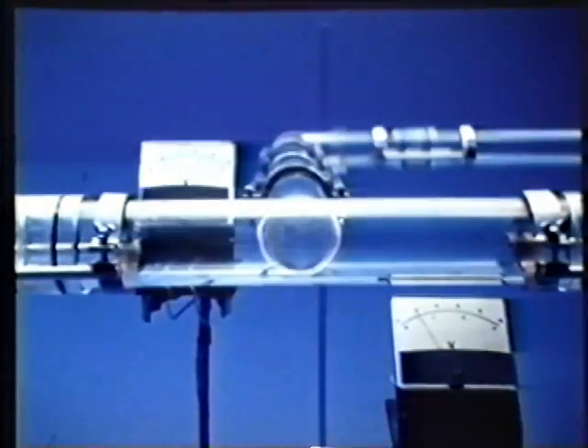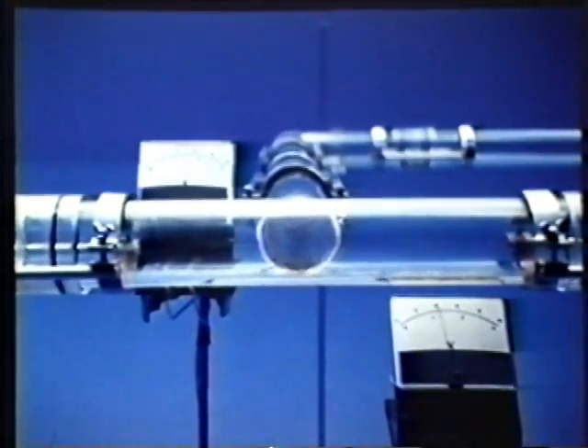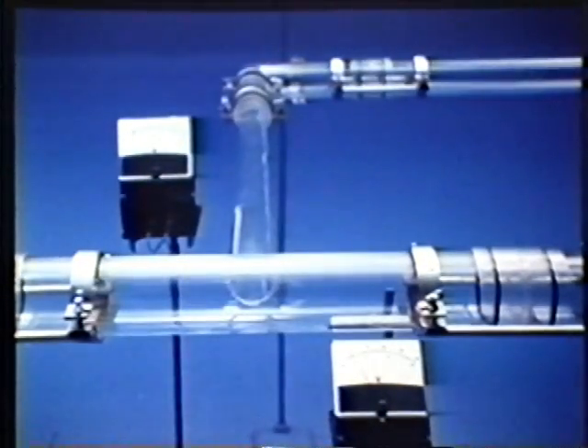The regional network, which branches out at numerous points, starts at the measuring and regulating stations. How does a flow of condensate behave at a branch point? This is the model of a pipeline with a branch line. The gas stream comes from the left. At this moment, the gas stream divides into two equal parts, and it appears that all of the liquid passes into the branch line. When the gas flow entering the branch line is lowered to 30%, all of the liquid still continues to flow into the branch line. It is not until a small part of the gas stream passes into the branch line that liquid flows straight through. In most cases, the liquid flow does not divide at a branch point, but either goes straight on or into the branch. Hence, the liquid flow shows a distinct route preference.